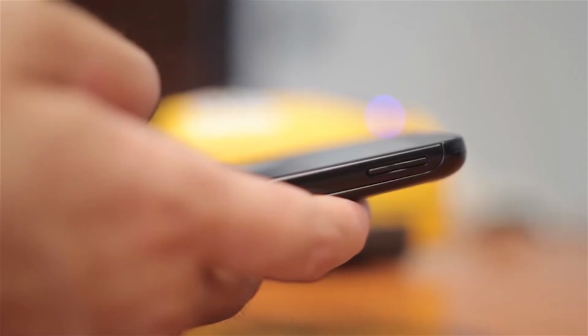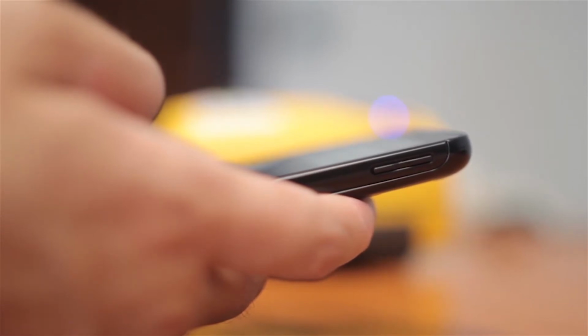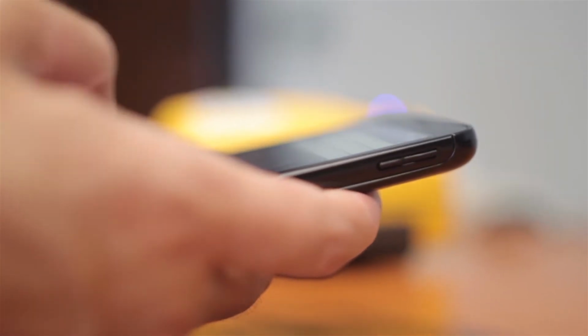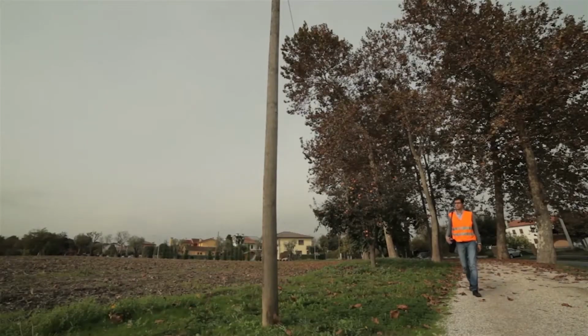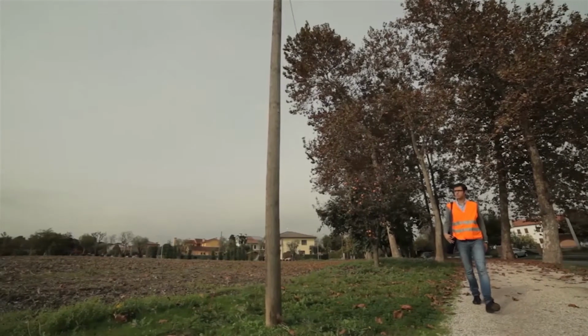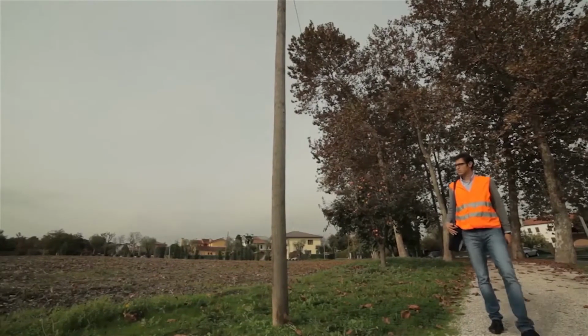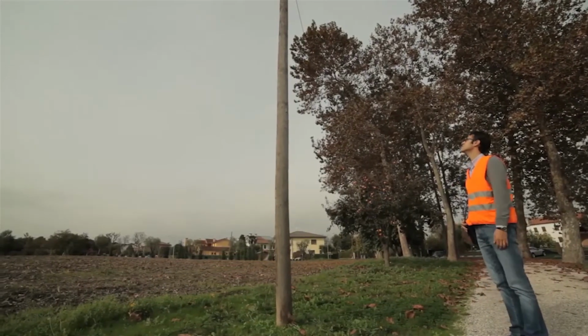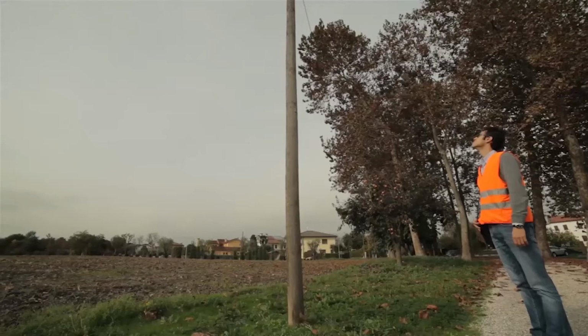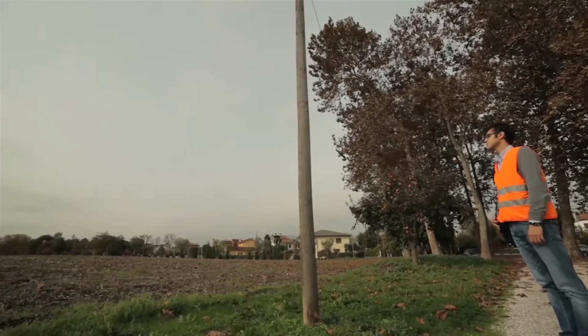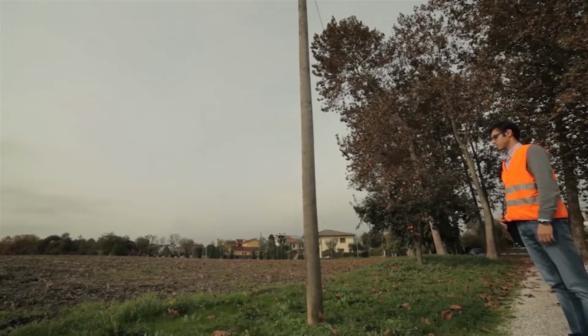The CXI PT5500 device uses innovative analysis techniques to measure the strength of wooden utility poles typically used in the telecom and electricity sectors. Using patented technology, the device is used to report the ultimate breaking strength, UBS, of a pole. By UBS we mean an objective measurement of the overall strength of the pole, including below ground.